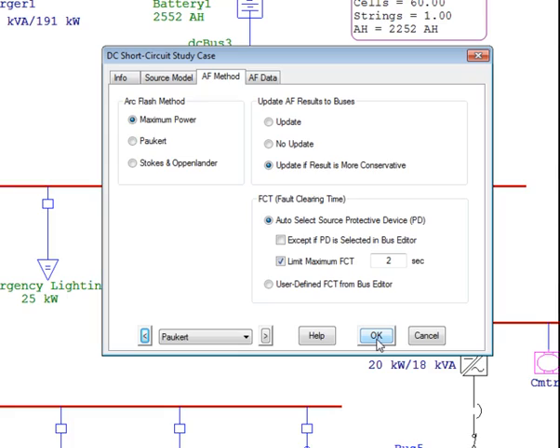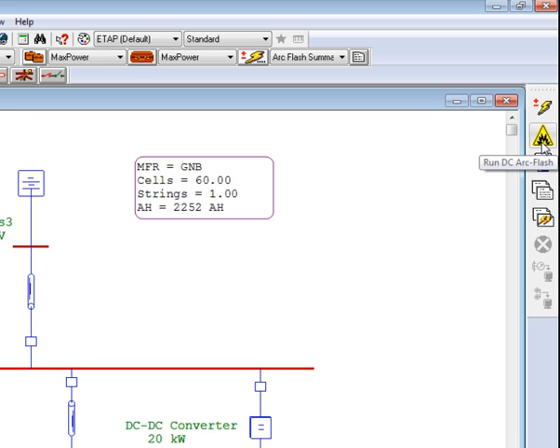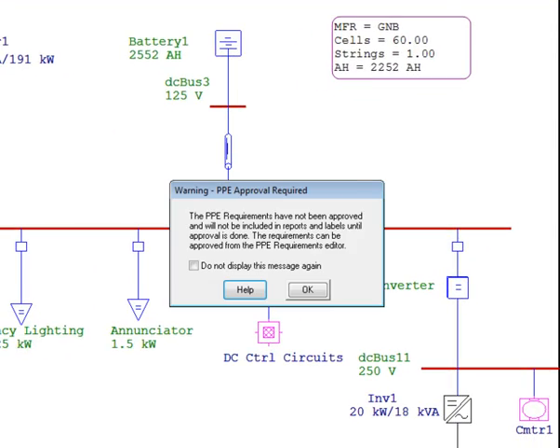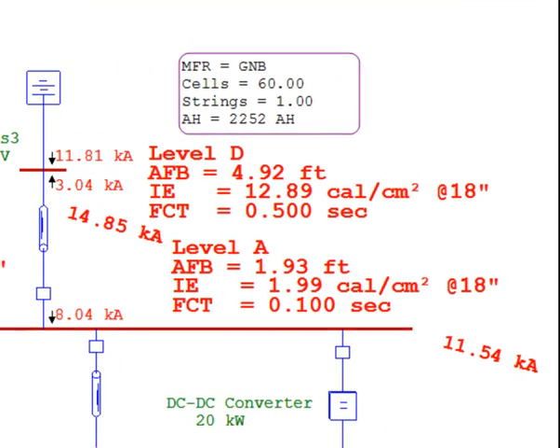Once we have selected the proper arc flash method, select OK. Now, let's proceed to run the arc flash calculations. These calculations can be run by pressing on the DC arc flash icon located in the top right hand corner. Click on it and the results will be displayed on the one line diagram. I would like to show the results around the battery terminals. If we zoom into that area, we will see that at the fault location at the battery terminal, we will get an incident energy of 12.89 calories per centimeter square at a working distance of 18 inches and a fault clearing time of half a second.